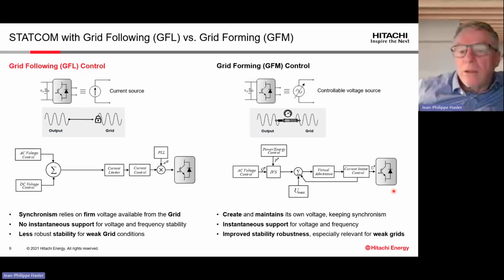The difference with grid forming nowadays is, as I have said, that the current through the converter is mainly defined by the virtual impedance. Each time you get a perturbation in the grid, the current will be defined by the virtual impedance. The only times we have to change the phase angle of the voltage, and that has to be done very slowly, with a bandwidth below a certain frequency, is, for example, to control the power or the energy we want to exchange between the STATCOM and the grid.